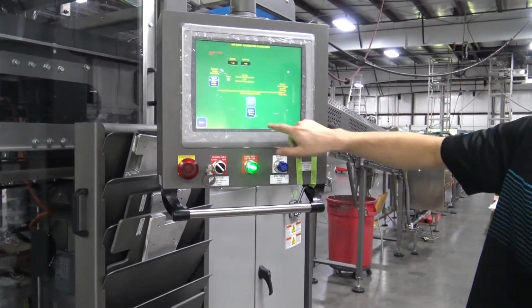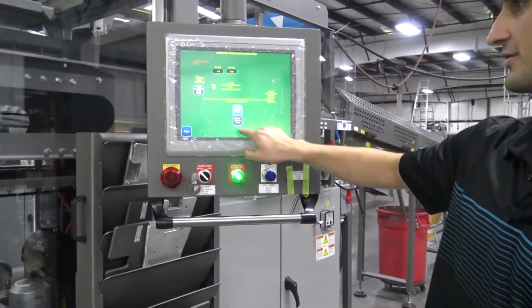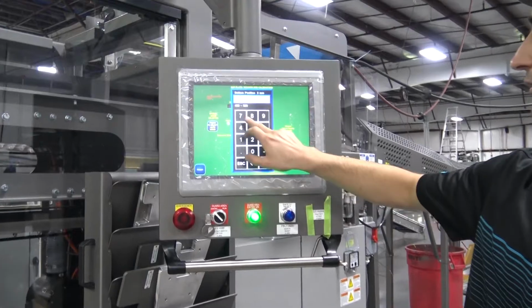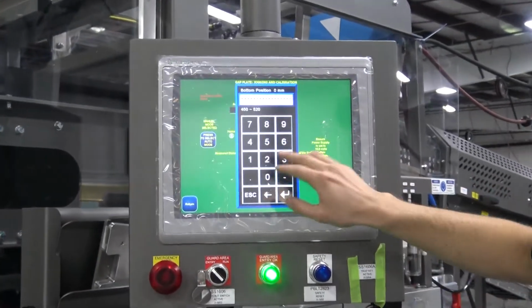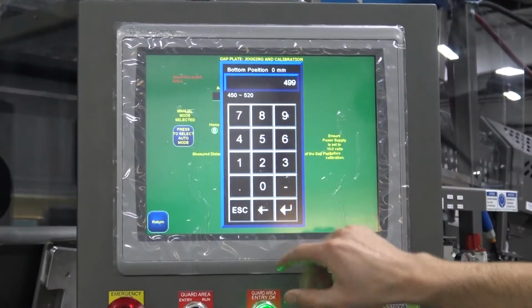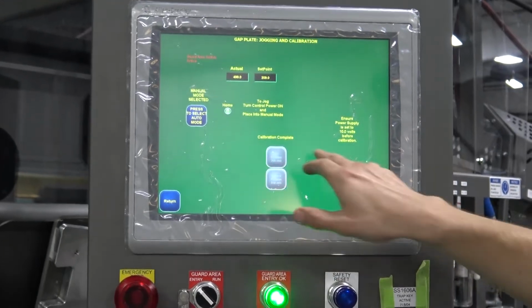Now we have this bottom position numeric input box, and the range is 450 to 520, so 499 is probably a good measurement. I enter that, and calibration is complete.